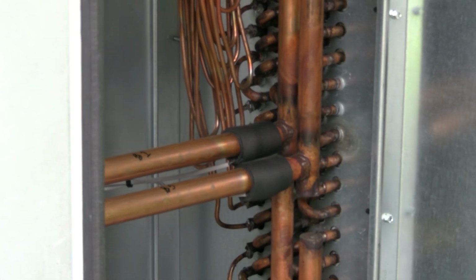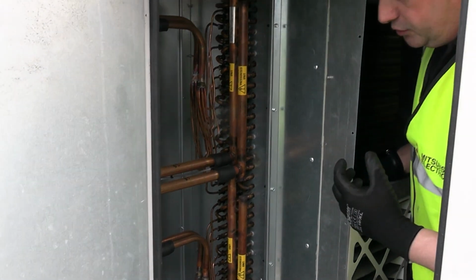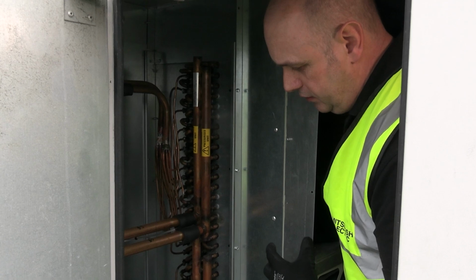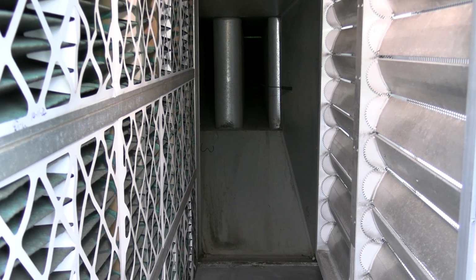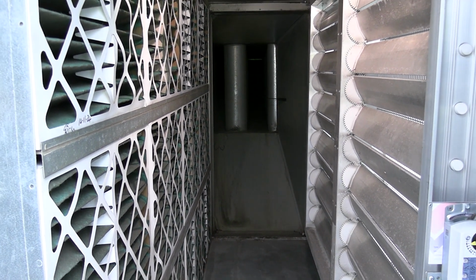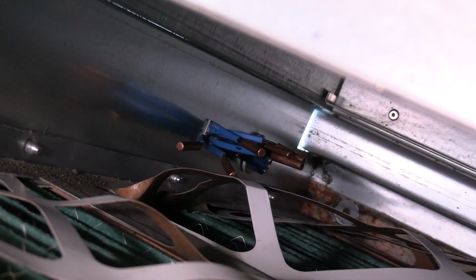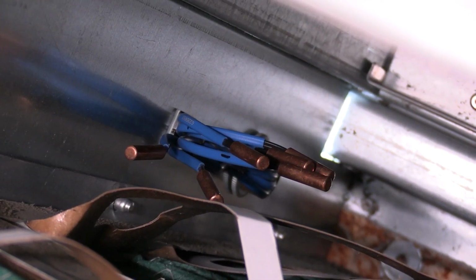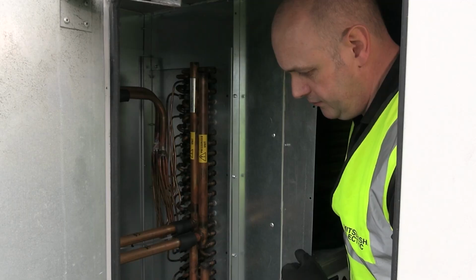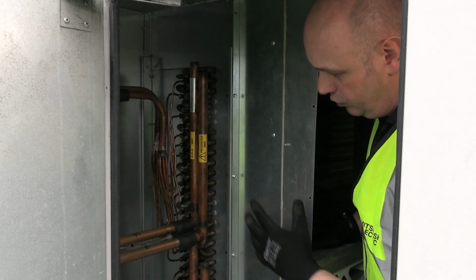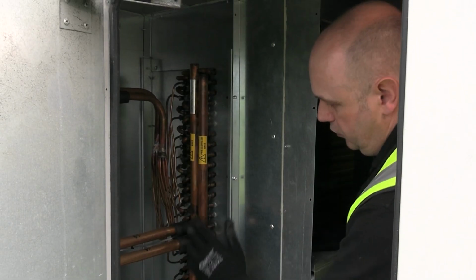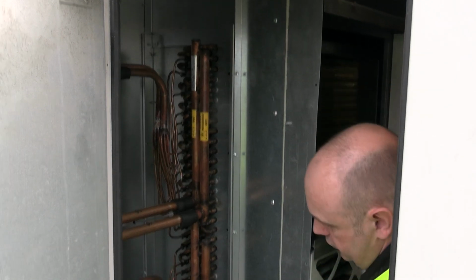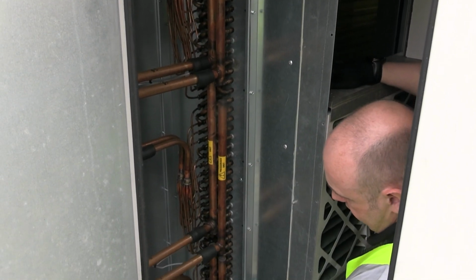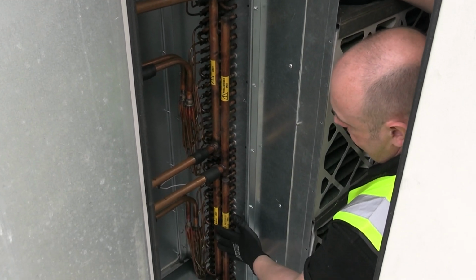Now in this particular application, what they're actually doing is they're measuring a common temperature. So if we have a look inside the actual unit, you'll see that it's actually measuring the supply air temperature onto the actual coil itself. So that's the way we're controlling that. Again, that information is being fed back to the PAC-IF. This particular one, say, is made up of 6 coils there. So you see there's a top coil, top set of coils there, got 2 there, 2 sets of coils down here, and the bottom set of coils there, so they've interlaced it.